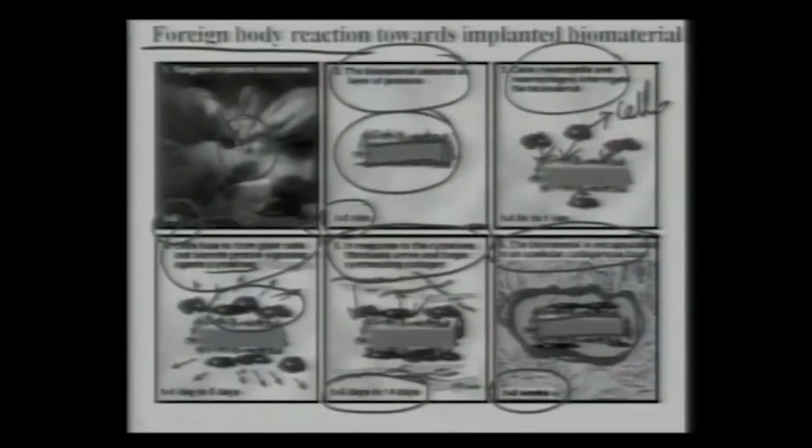So essentially it starts with t equal to 0 and goes to t equal to 3 weeks. So the entire process takes almost 3 weeks or 21 days. And that is one of the reasons why many of the short-term implantation tests to see whether a biomaterial is biocompatible in vivo, people do up to 12 weeks, because your initial reaction takes place over even 3 weeks, then you see whether it causes inflammation to the neighboring tissues or cells, and that entire thing should be studied up to a sufficient time period, and that is the reason it takes 12 weeks.